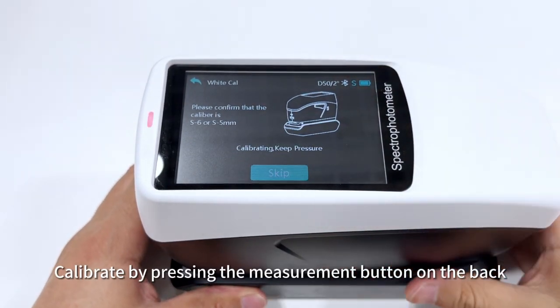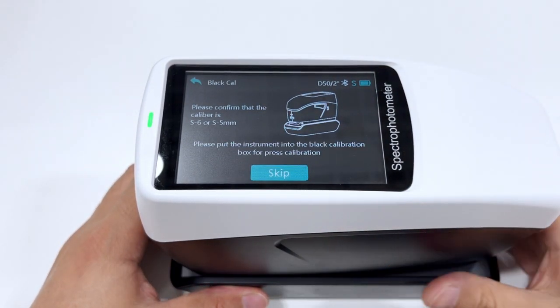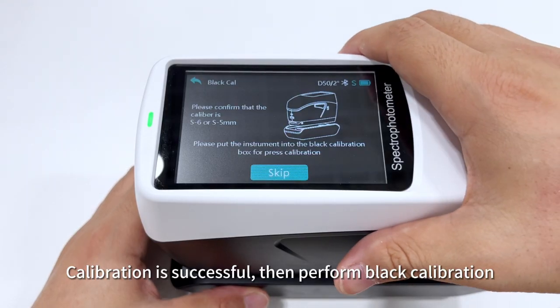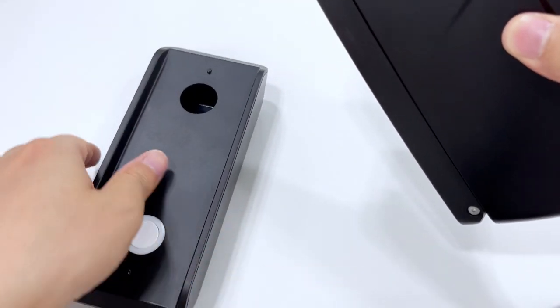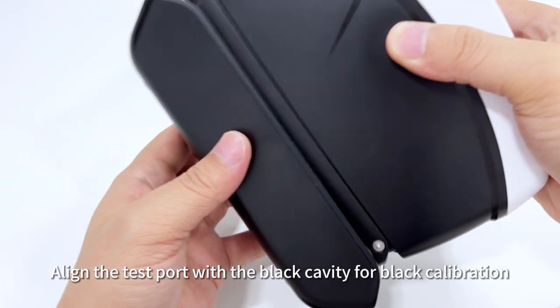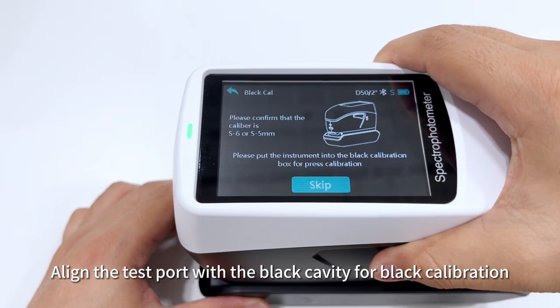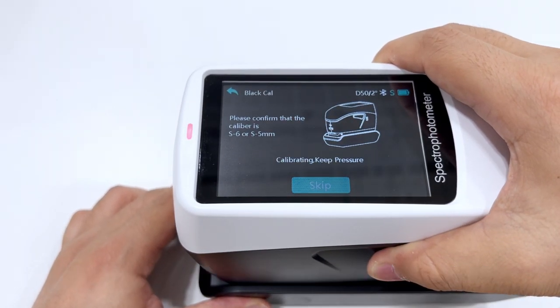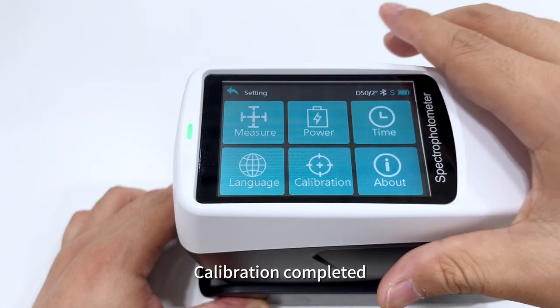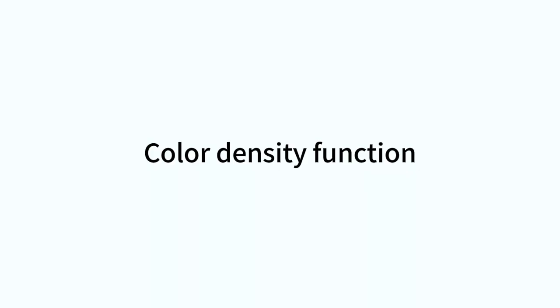Calibrate by pressing the measurement button on the back. Calibration is successful, then perform black calibration. Align the test port with the black cavity for black calibration. Calibration completed. Color density function.